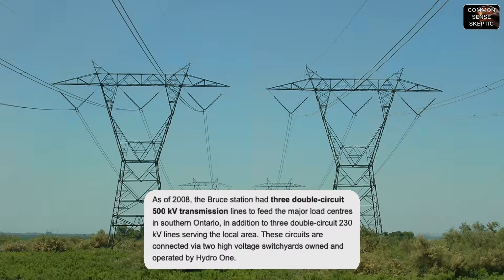With Musk's solar farm, we're looking at distributing terawatts, not gigawatts. For argument's sake, and this will be completely ridiculously conservative compared to what would actually need to be built, let's say we are stringing a single set of circuits between Utah and a central point for each state for distribution throughout the state. We'll use the known costs for 500 kV double circuit lines and 230 kV double circuit lines, such as those used by the Bruce station, using 3 of each.